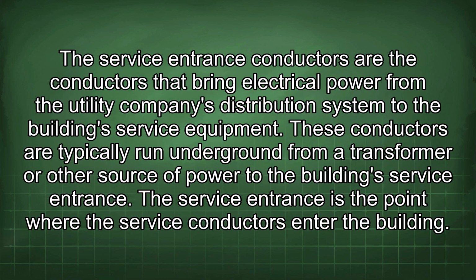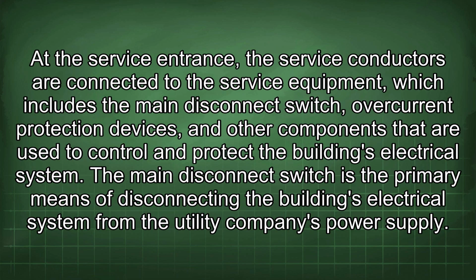The service entrance conductors are the conductors that bring electrical power from the utility company's distribution system to the building's service equipment. These conductors are typically run underground from a transformer or other source of power to the building's service entrance. The service entrance is the point where the service conductors enter the building. At the service entrance, the service conductors are connected to the service equipment, which includes the main disconnect switch, overcurrent protection devices, and other components that are used to control and protect the building's electrical system.